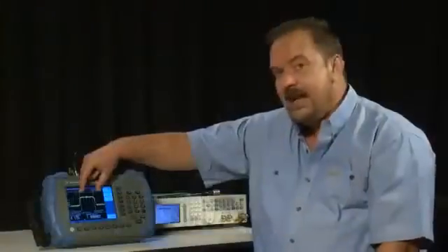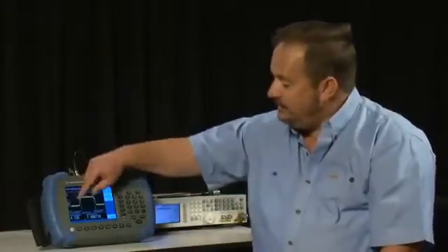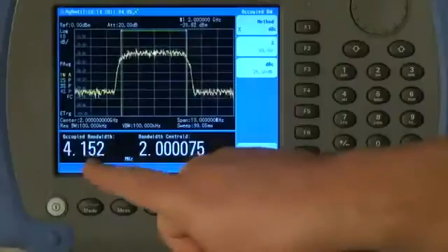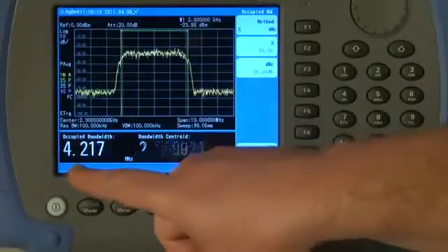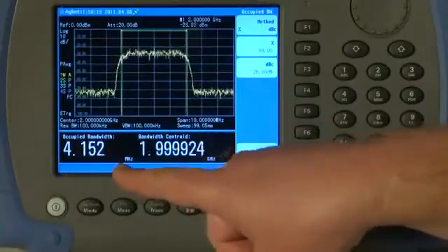What is happening here is the analyzer is automatically measuring within what bandwidth 99% of the power on the display is contained. That is varying slightly because of the noise on the signal, but you can see that the occupied bandwidth is about 4.1, maybe 4.2 MHz.